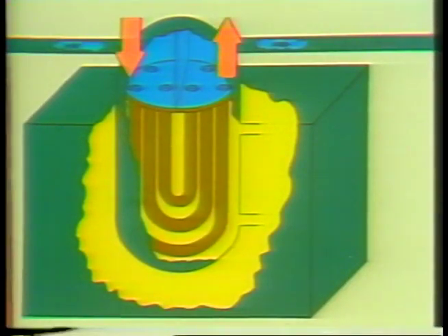In this bearing oil cooler, the cooling water flows through the tubes and the oil flows through the shell. This heat exchanger is used to cool the bearing oil from the main turbine. The same principles which govern heat transfer in a feed water heater also govern heat transfer in a bearing oil cooler. These are the flow of cooling water and oil and the temperature difference between them.